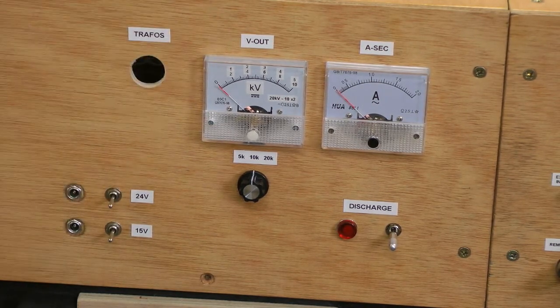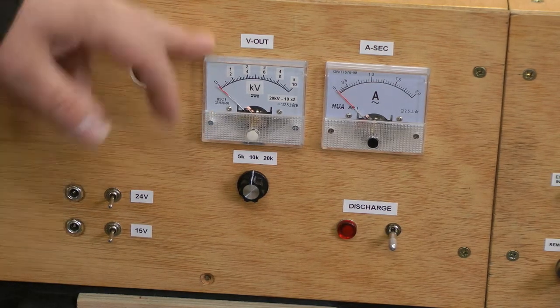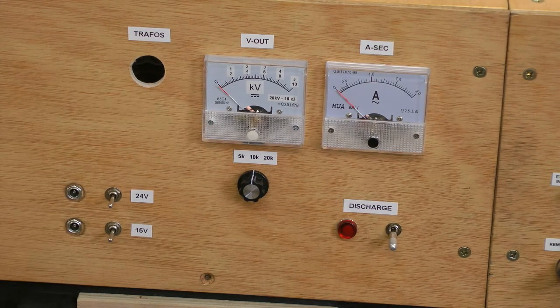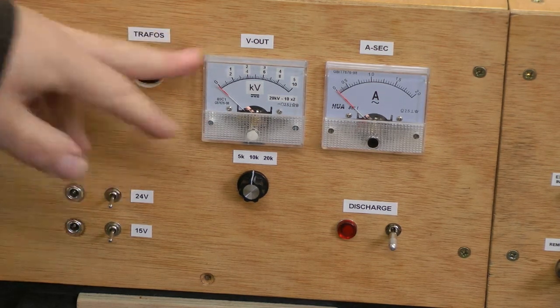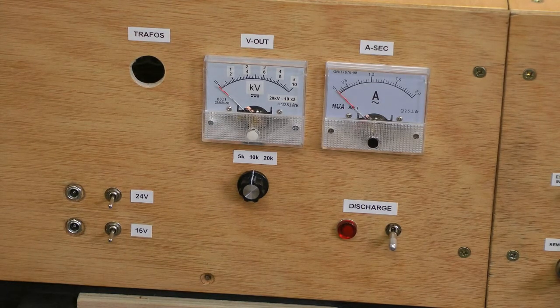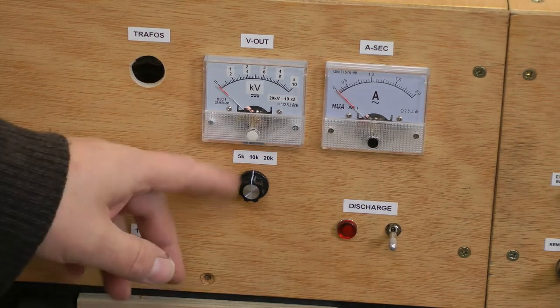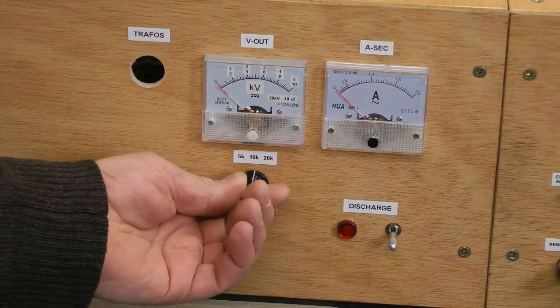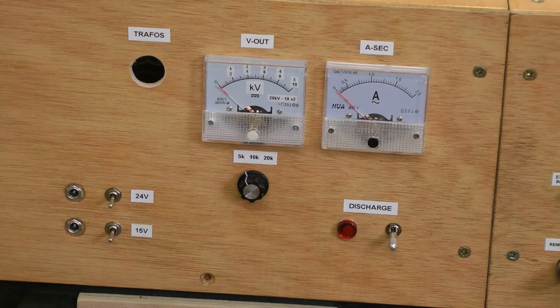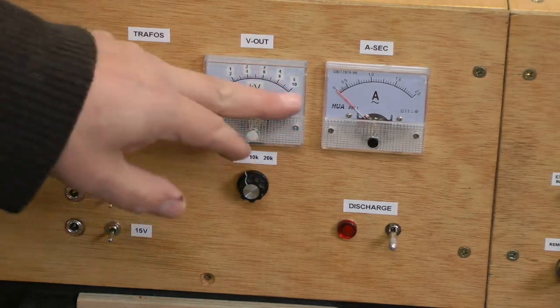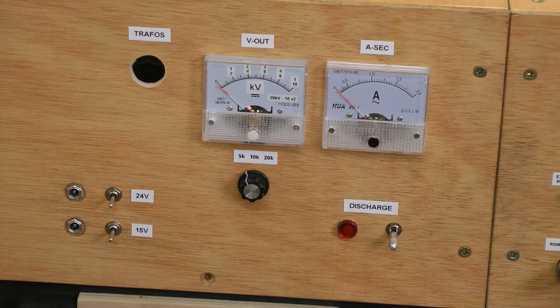This is a whole subsystem in there, which is basically a 1 milliamp DC current meter, which has a resistor chain in front of it. So 1 mega ohm, 2 watt resistors. If you put 20 of them in series, then 20 kilovolts is going to go down to 1 milliamp. If you put 10 of them, then 10 kilovolts is going to go down to 1 milliamp, and so on and so forth. So I've got 3 ranges that are selected here: 5 kilovolts, 10 and 20. Then I use one of these Dymo machines to print out sticky labels, and I can stick them on the screen. Essentially I can turn a 1 milliamp meter into any meter that I want with the divider.